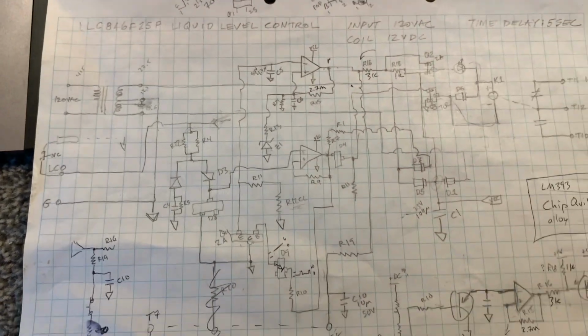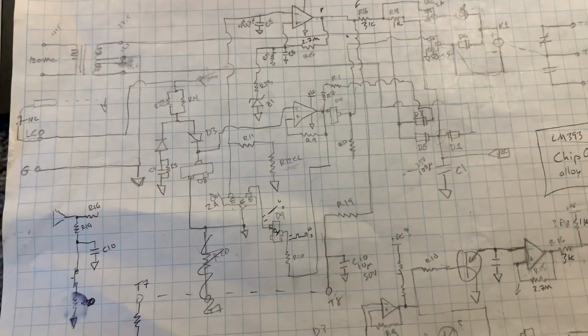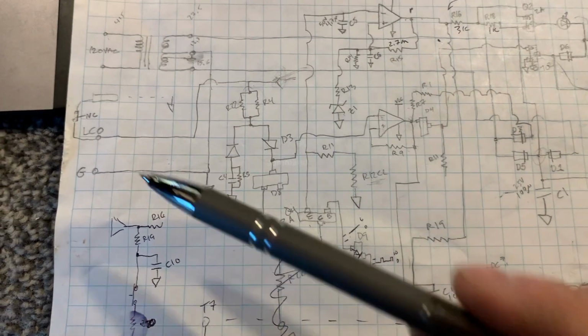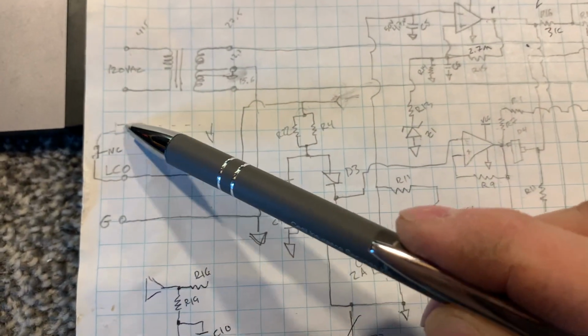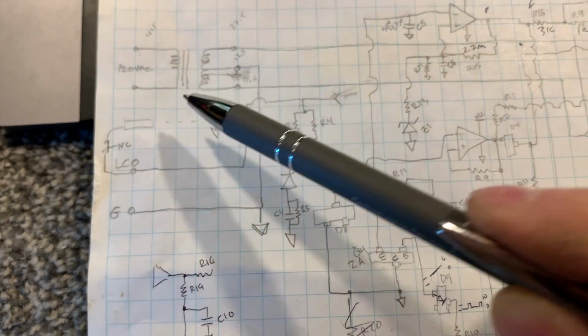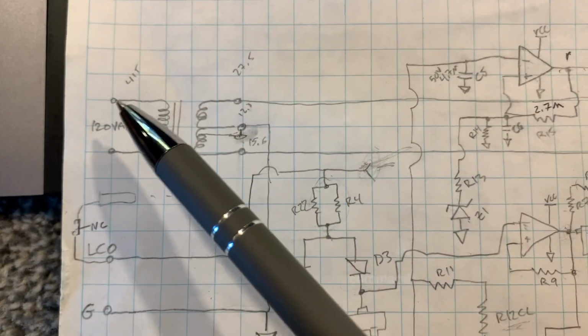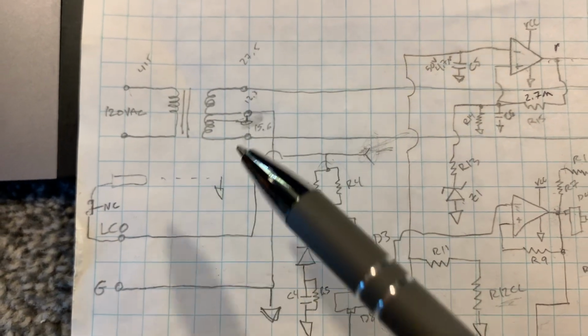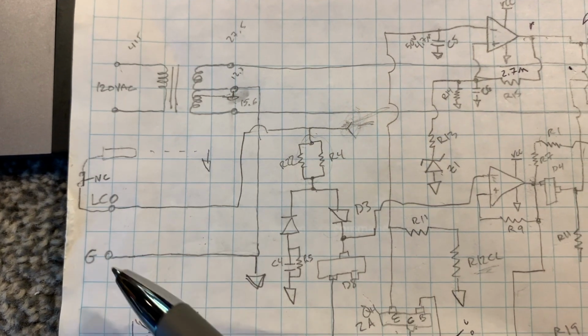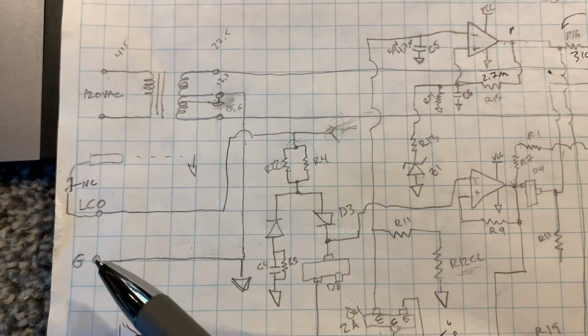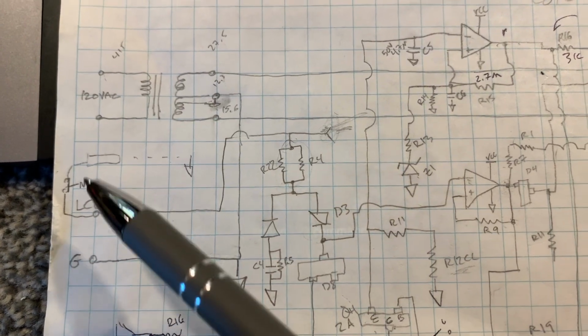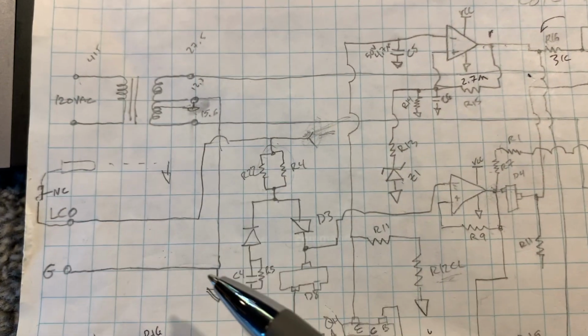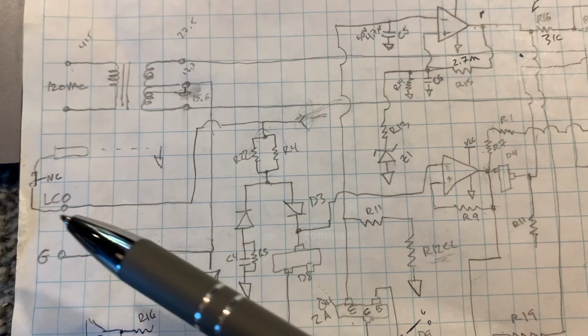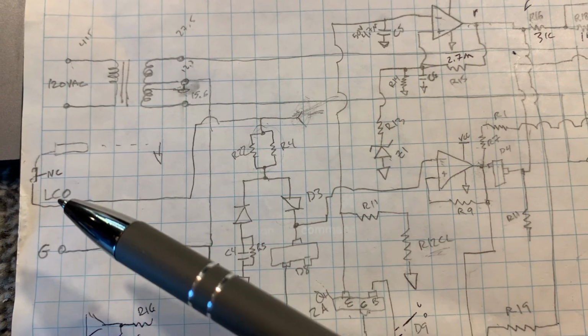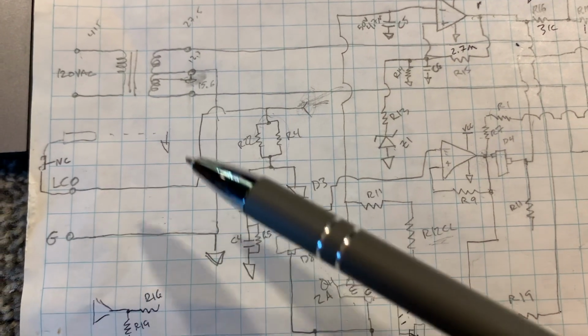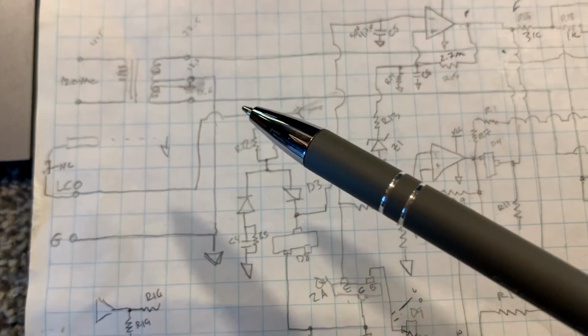I want to go through this schematic. This is a pretty rough schematic of what the board has. We have the low water cutoff probe right here, and it comes in. We have the 120 volts AC center tap transformer, and then the ground plane, which has a separate ground connection just for the probe, and it's also tied into the power supply ground. So the resistance between these two terminals, the probe itself and the ground, creates a voltage divider circuit.